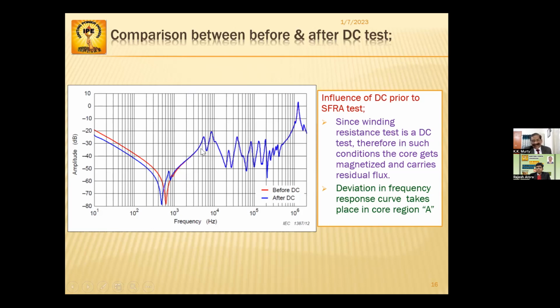In other frequencies, the difference is not there. Here you can see distinctly the difference. So the red color is before the DC test, before the transformer core is magnetized, and blue is after the DC test. Here you can see the curve is different because the core is magnetized, the deviation is there, and in the lower frequency also it is coming here, unlike this red one.